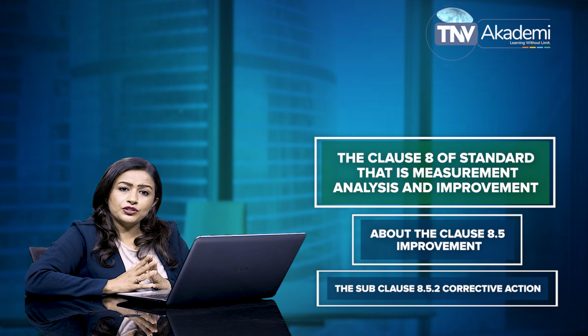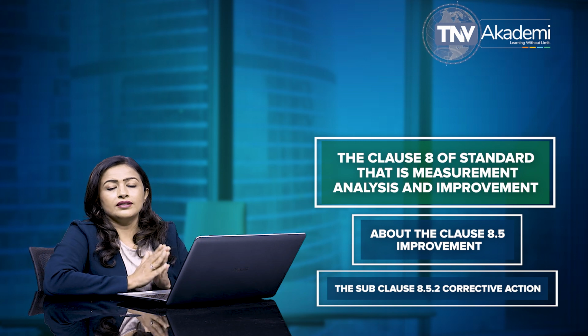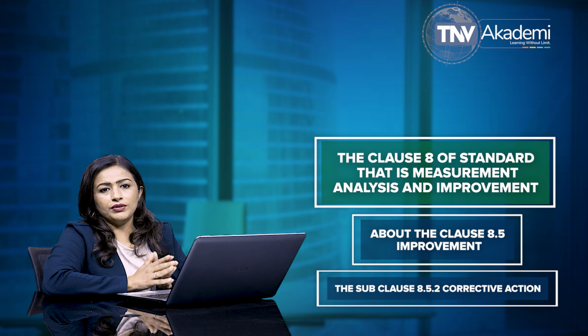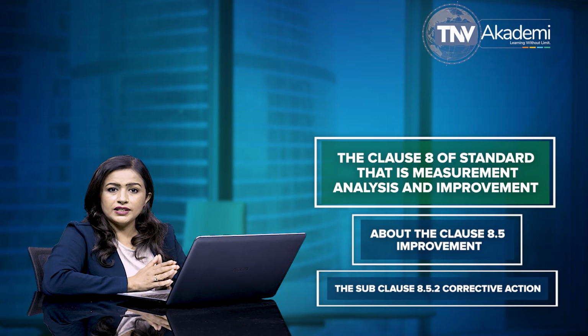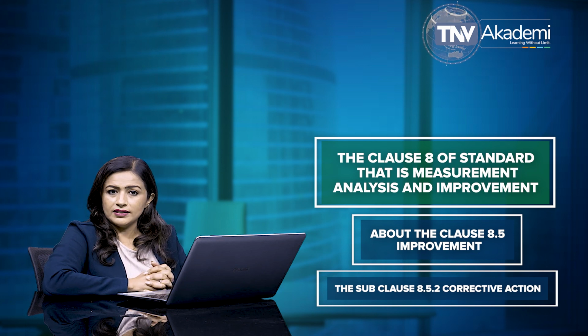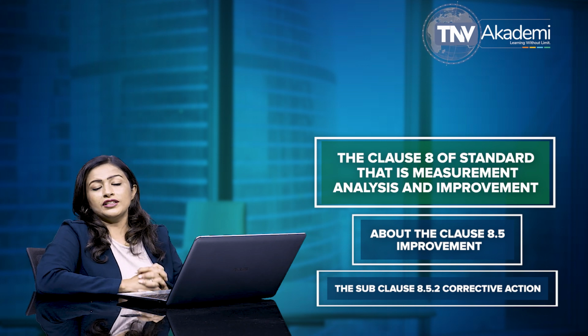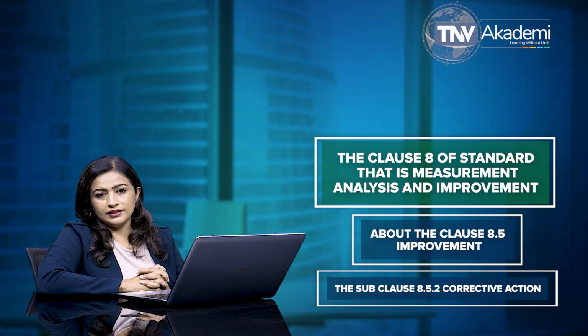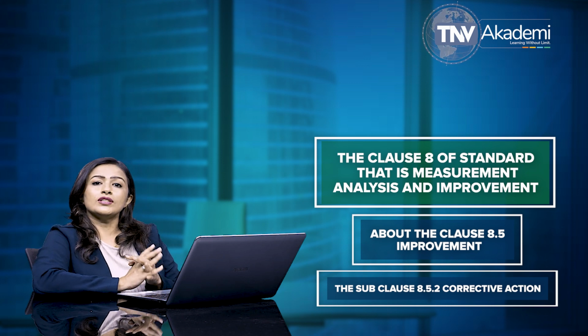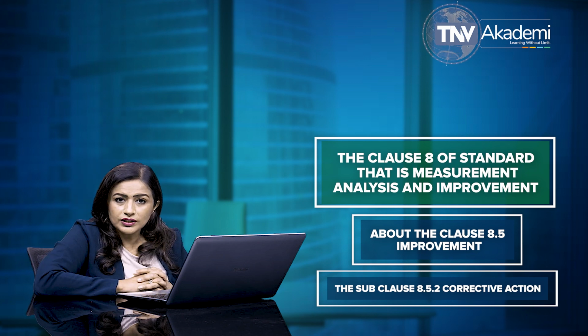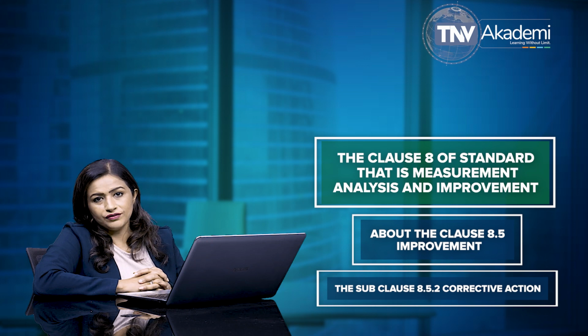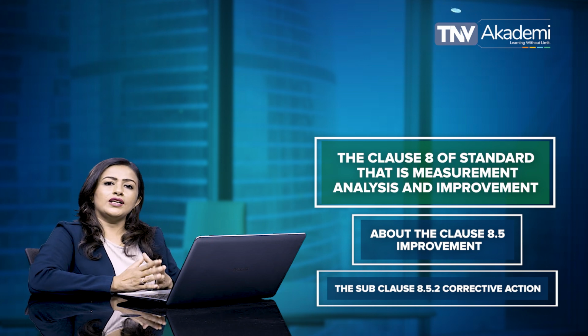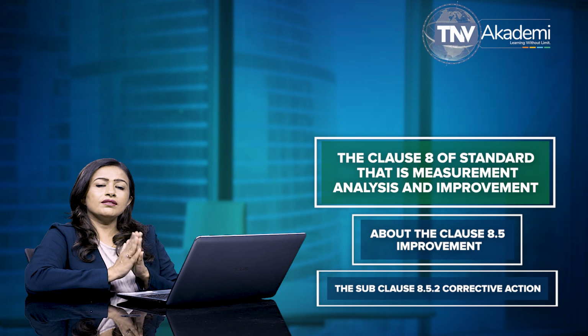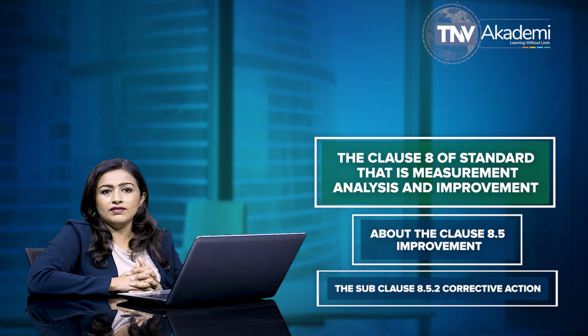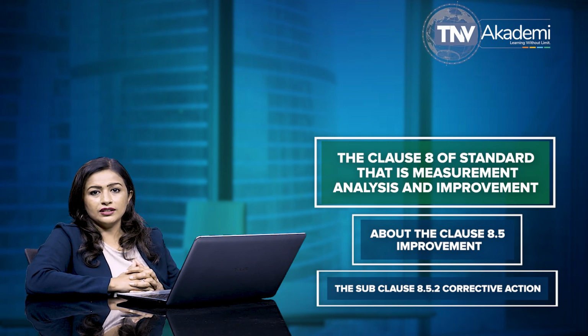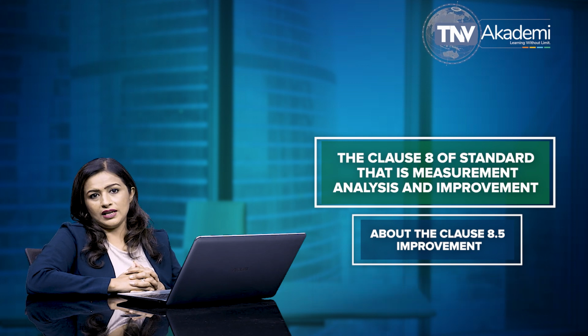Verifying that the corrective action does not adversely affect the ability to meet applicable regulatory requirements or the safety and performance of the medical device, and reviewing the effectiveness of corrective action taken. Further, subclause 8.5.2 of ISO 13485 states that the organization is required to maintain the records of the results of any investigation and of action taken to meet the requirements of the standard.